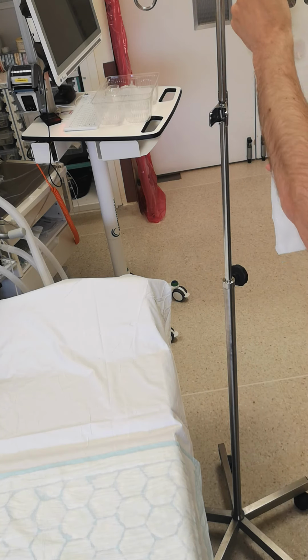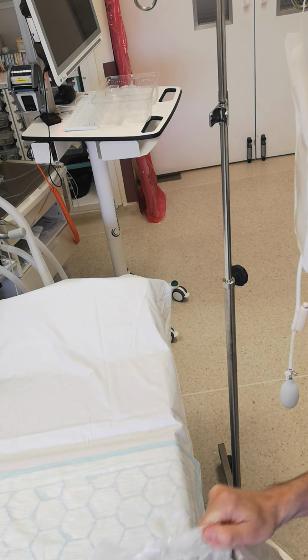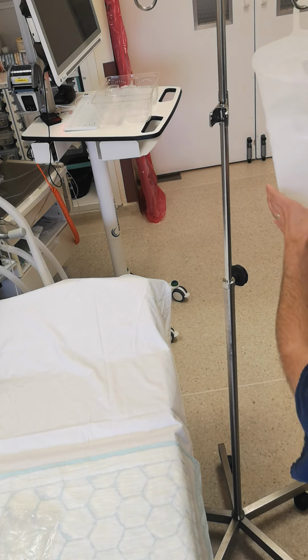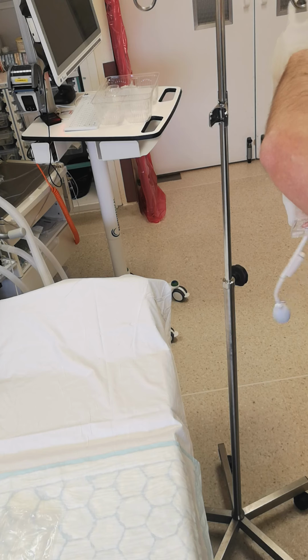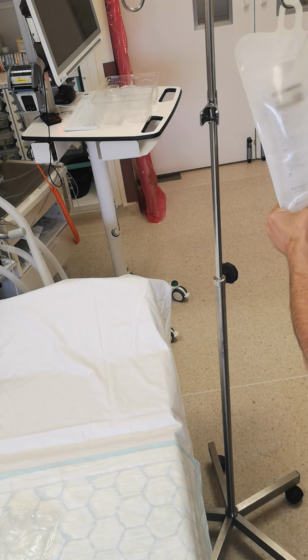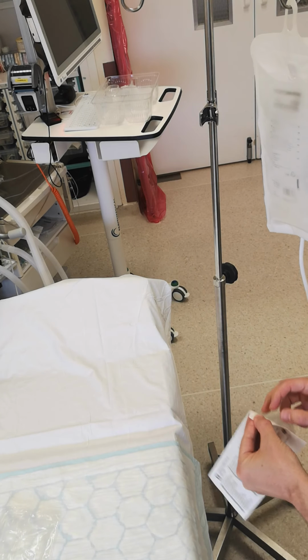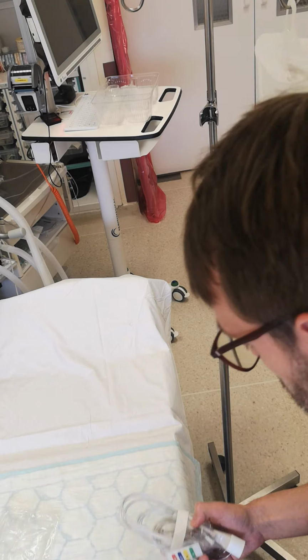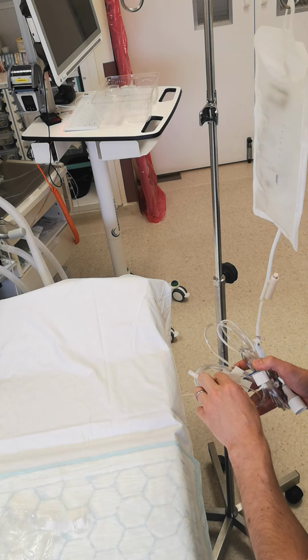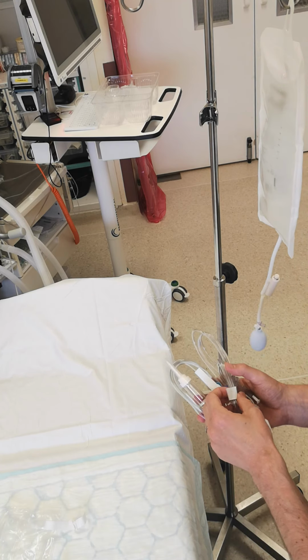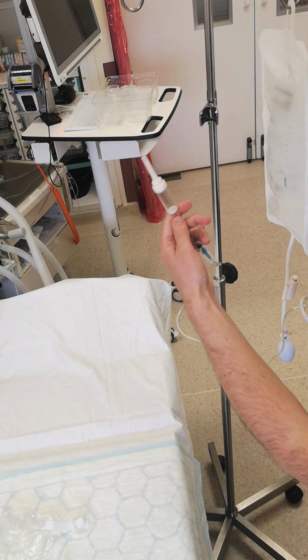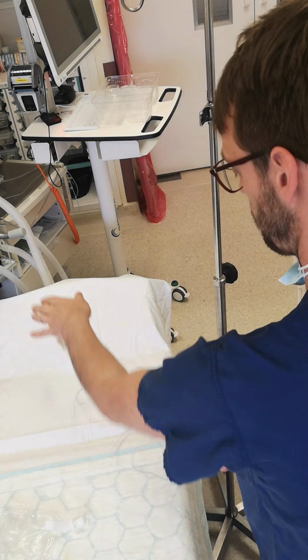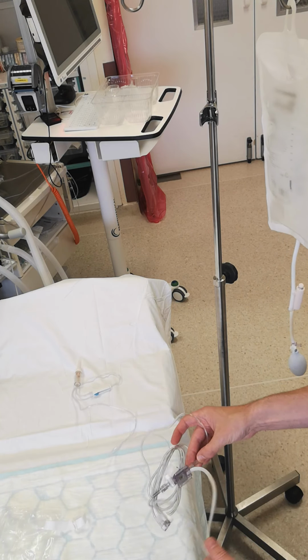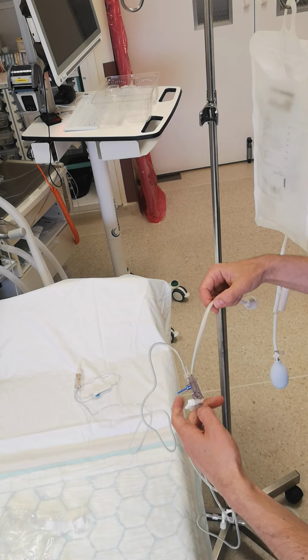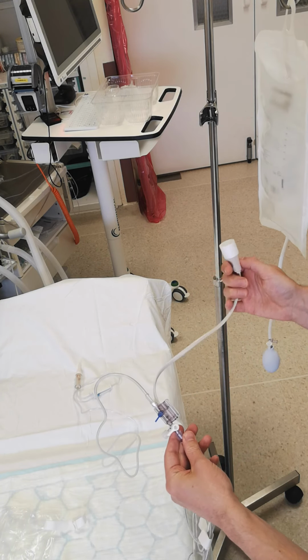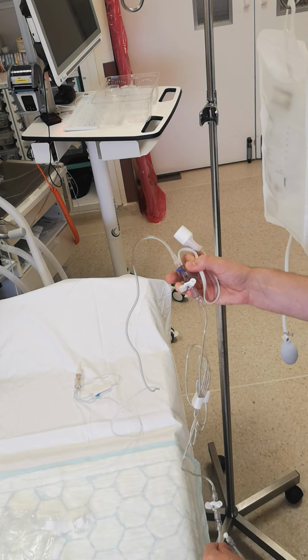So what I normally do is put the pressure bag up first. You can put the bag in to here, ready. Open the transducer pack. That can all be opened like that. So the pieces are the bits: the spike will go into the bag with the roller valve. That will lead down to the transducer, and that bit will be the electrical cable to the machine, and then it will continue down this way to the patient end.